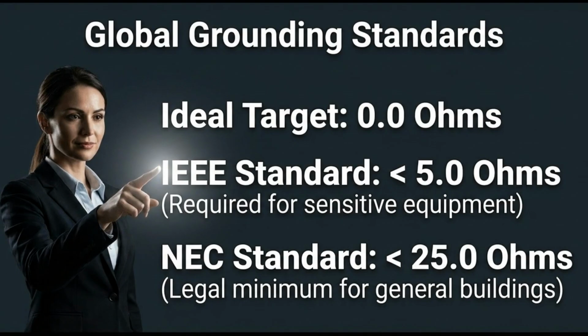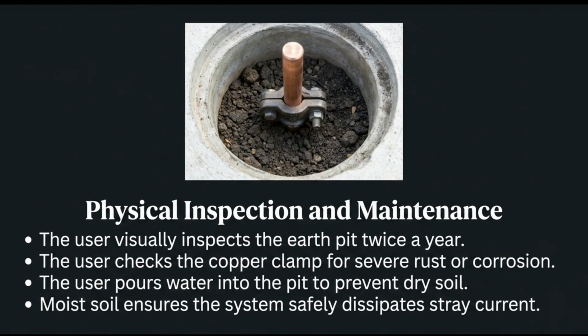When evaluating your results, refer to global standards. The ideal target is 0 ohms, while the IEEE standard requires less than 5 ohms for sensitive equipment, and the NEC mandates less than 25. Finally, remember to perform routine physical inspections twice a year. Check for corrosion on your copper clamps and ensure the soil remains moist to keep your earthing system functioning safely.